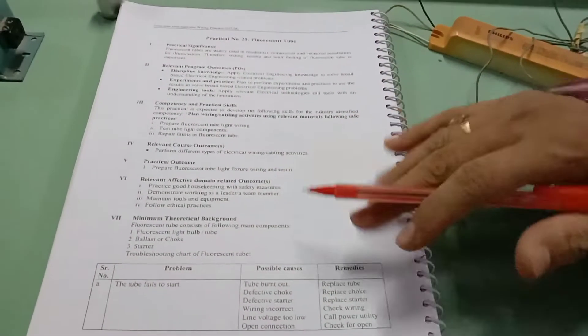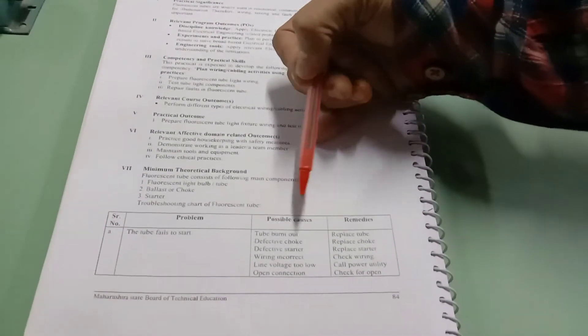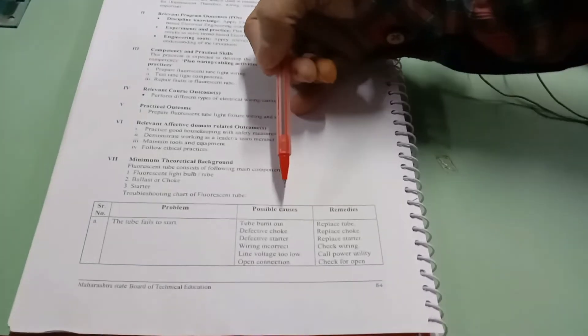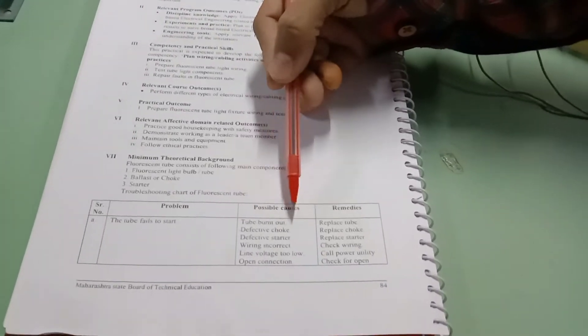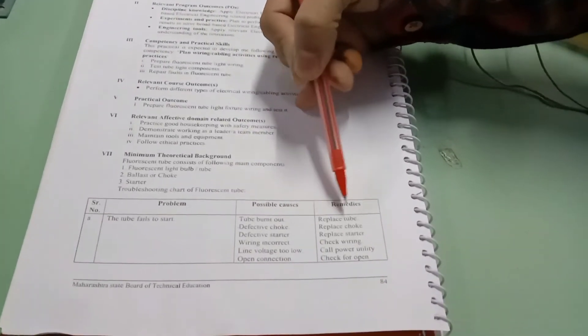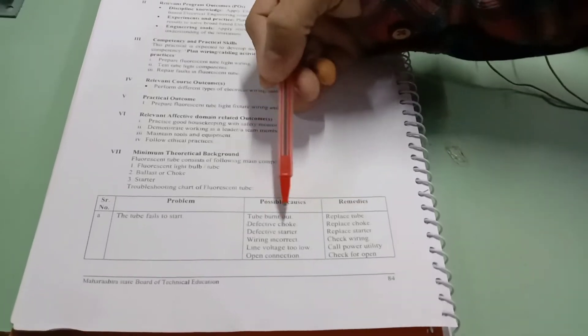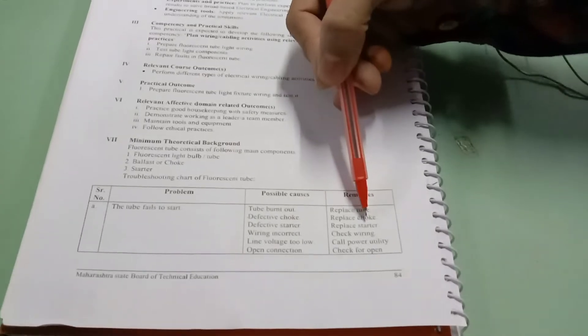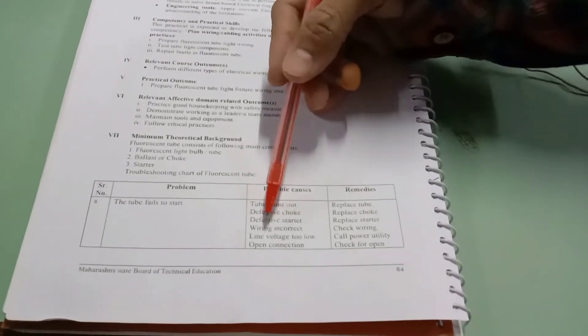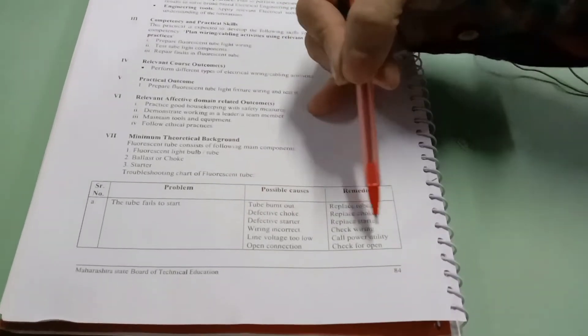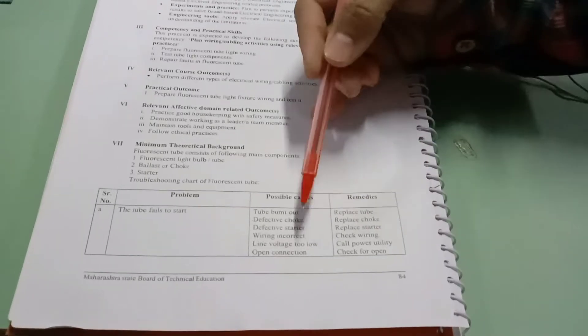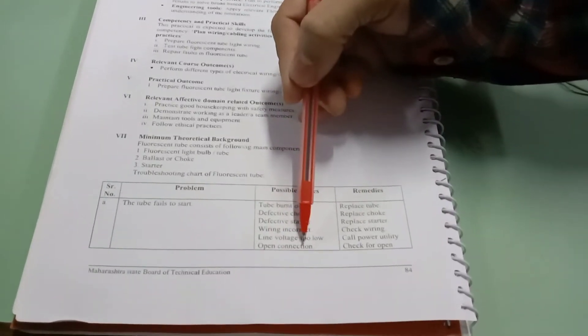Before studying this practical we should know about the troubleshooting charts. When the tube light fails to start, the possible cause is tube burnout. Remedies are we have to replace that tube light. If the defective choke is there then we have to replace. If defective starter is there then we have to replace it. If line voltage is too low then we have to call the power utility. If open connections are there then we have to check for the open connection.